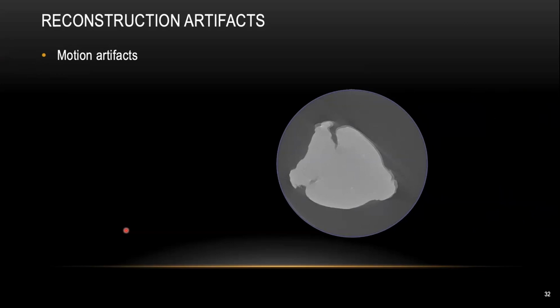That's the reason when you go to a hospital and take some CAT scan, the doctor always says, hold the breath, don't move. Any kind of movement is going to destroy your X-ray image. So you can see from this picture on the screen here, it's a cross-section image for a piece of sample, but you can look very closely over here. We do have some kind of double image, and down here, there's no double image. That's a clear indication the sample might be moving during the scanning. So that's the so-called motion artifact.